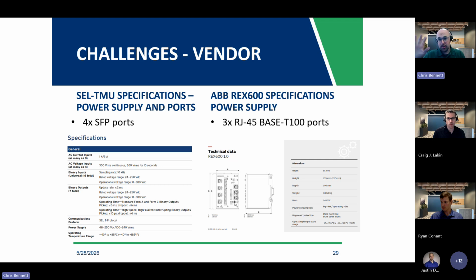As an example here, just taking from the cut sheets, on the left, I took the SEL TMU, which is the merging unit that would sit out at the device. And in the specification, it allows for 4 SFP ports. SFP is small form factor pluggable. It means that you can effectively use fiber or copper Ethernet cables if you so desire, depending on your need and network and system. That's to get the communication back to the centralized device.